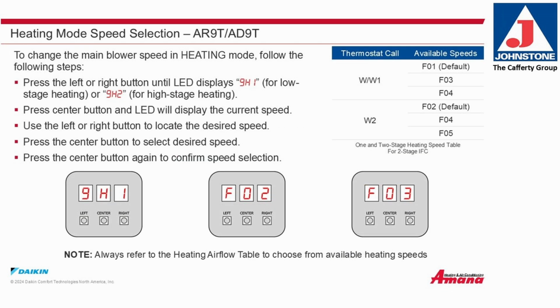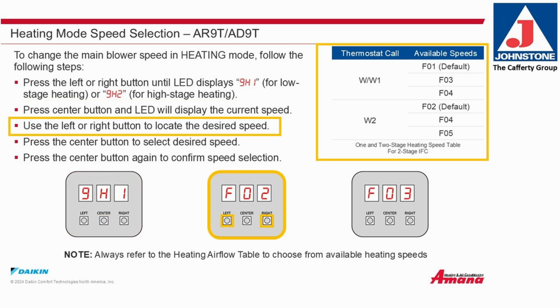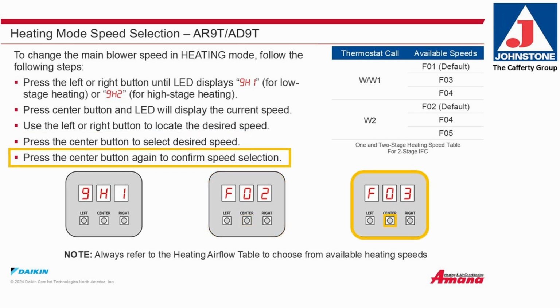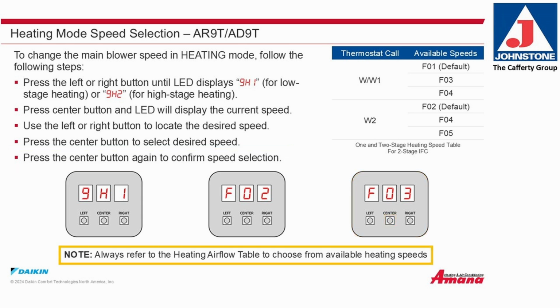Heating mode speed selection. To change the main blower speed in heating mode, follow these steps. Press the left or right button until the LED displays GH1 for low-stage heating or GH2 for high-stage heating. Press the center button and the LED will display the current speed. Use the left or right buttons to locate your desired speed. Press the center button to select that desired speed. Press the center button again to confirm speed selection. Always refer to the heating airflow table to choose the available heating speeds.